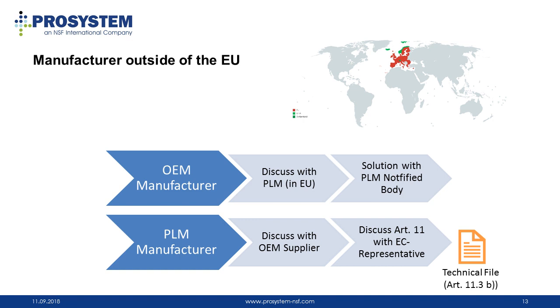And the remaining notified bodies have got a lot of work to do with the registration process and all the requirements for the MDR, and still maintaining the registrations under the still existing MDD. So please keep in mind, if you need to have some discussions with your notified body or the notified body of the PLM, do that really early, because it is really hard to get in touch with the notified bodies, and it will be even harder in the coming months and years.